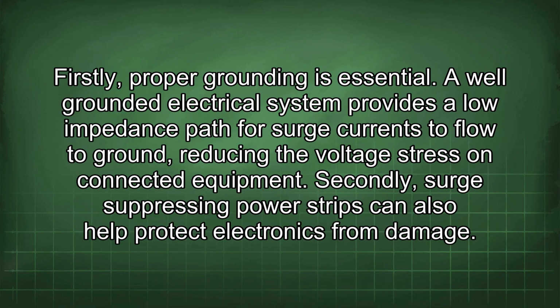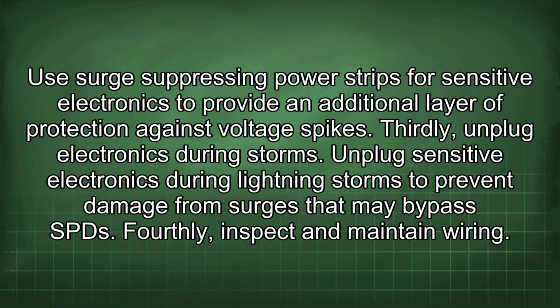Firstly, proper grounding is essential. A well-grounded electrical system provides a low-impedance path for surge currents to flow to ground, reducing the voltage stress on connected equipment. Secondly, surge-suppressing power strips can also help protect electronics from damage. Use surge-suppressing power strips with sensitive electronics to provide an additional layer of protection against voltage spikes. Thirdly, unplug electronics during storms. Unplug sensitive electronics during lightning storms to prevent damage from surges that may bypass SPDs.